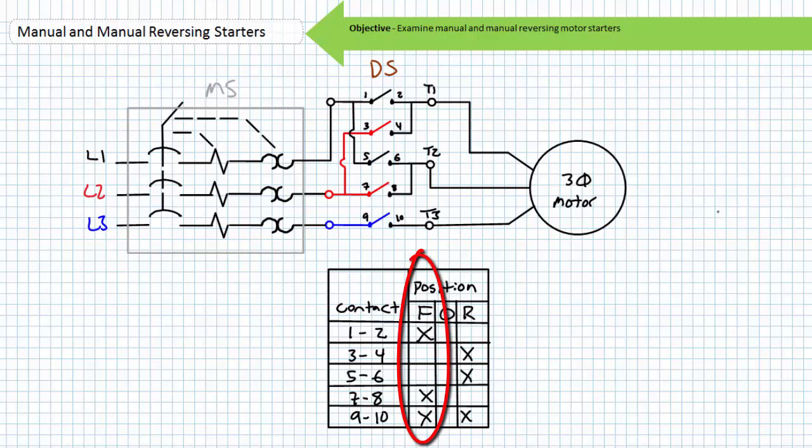When the drum switch is in the forward position and the motor starter is closed, the truth table illustrates that the phase sequence seen by the stator is L1, L2, L3. Let's say this rotates the motor clockwise for this particular application. However, when the drum switch is in the reverse position and the motor starter is closed, the truth table illustrates the phase sequence seen by the stator is L2, L1, L3. This would see the motor rotate counterclockwise.